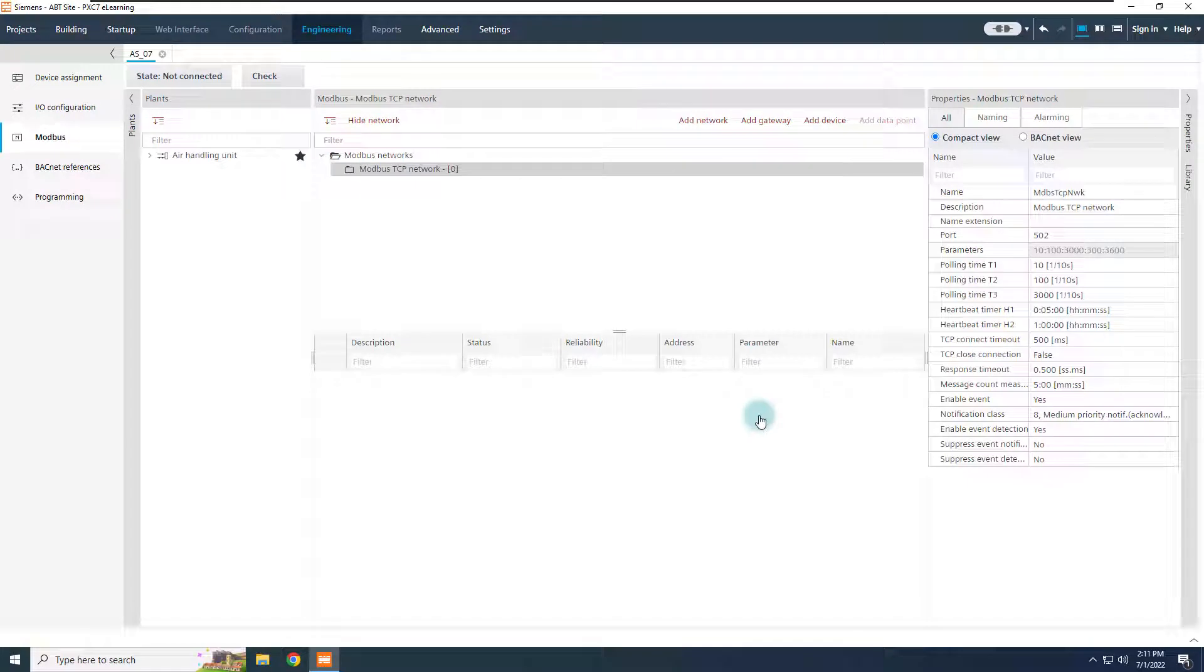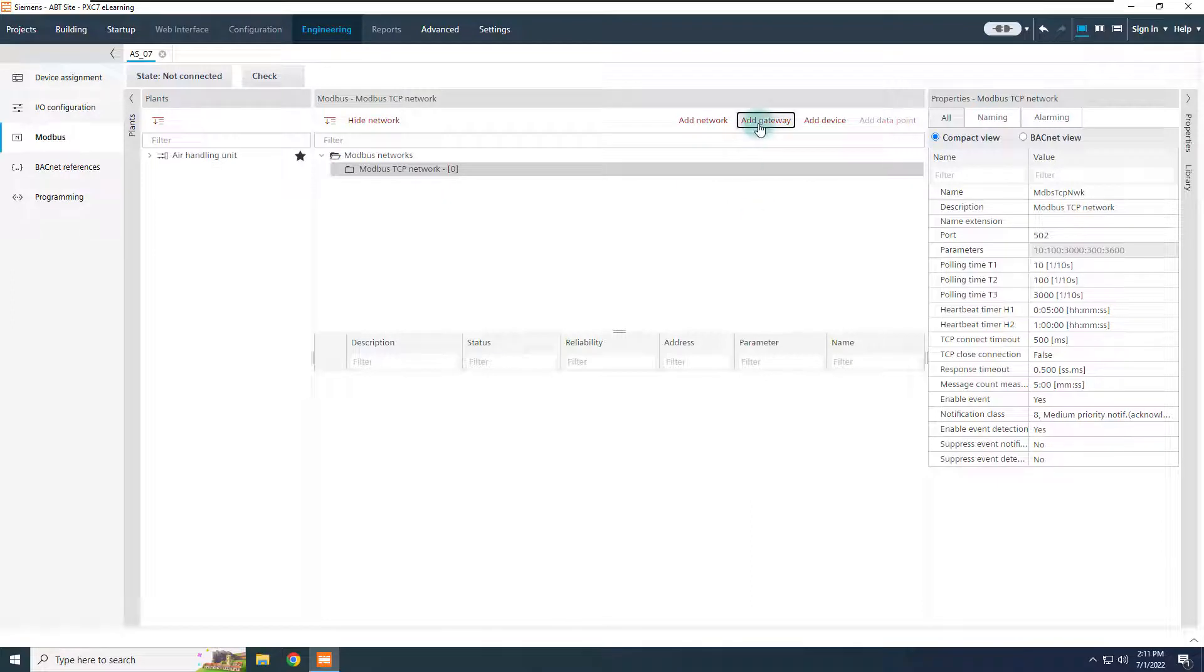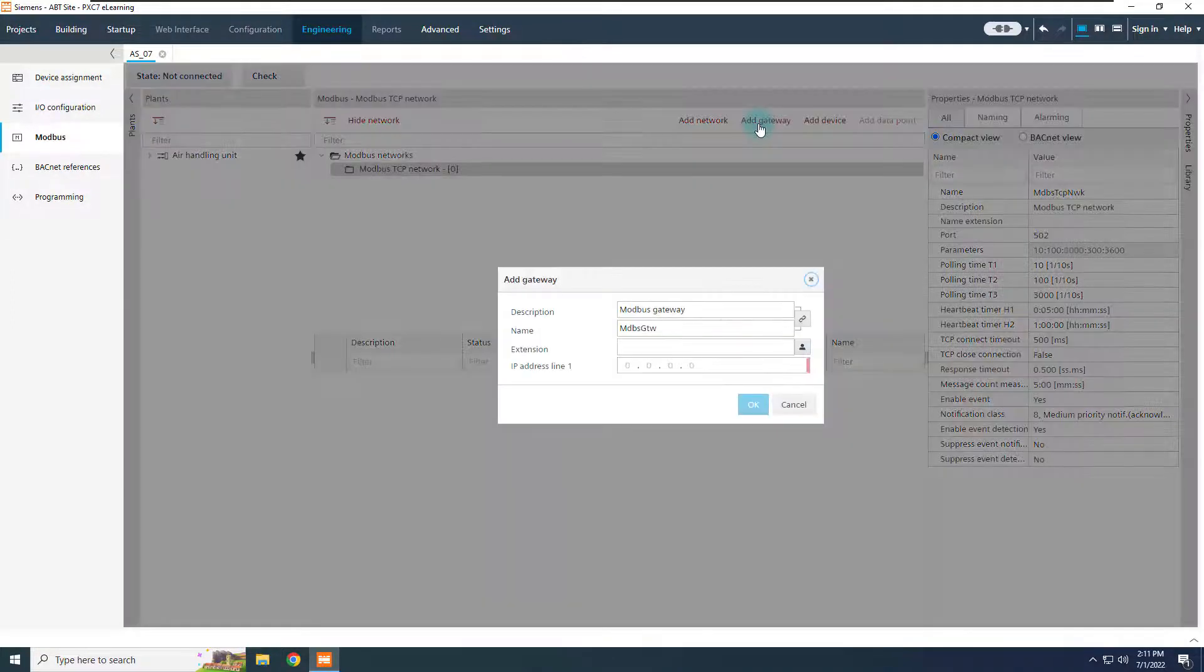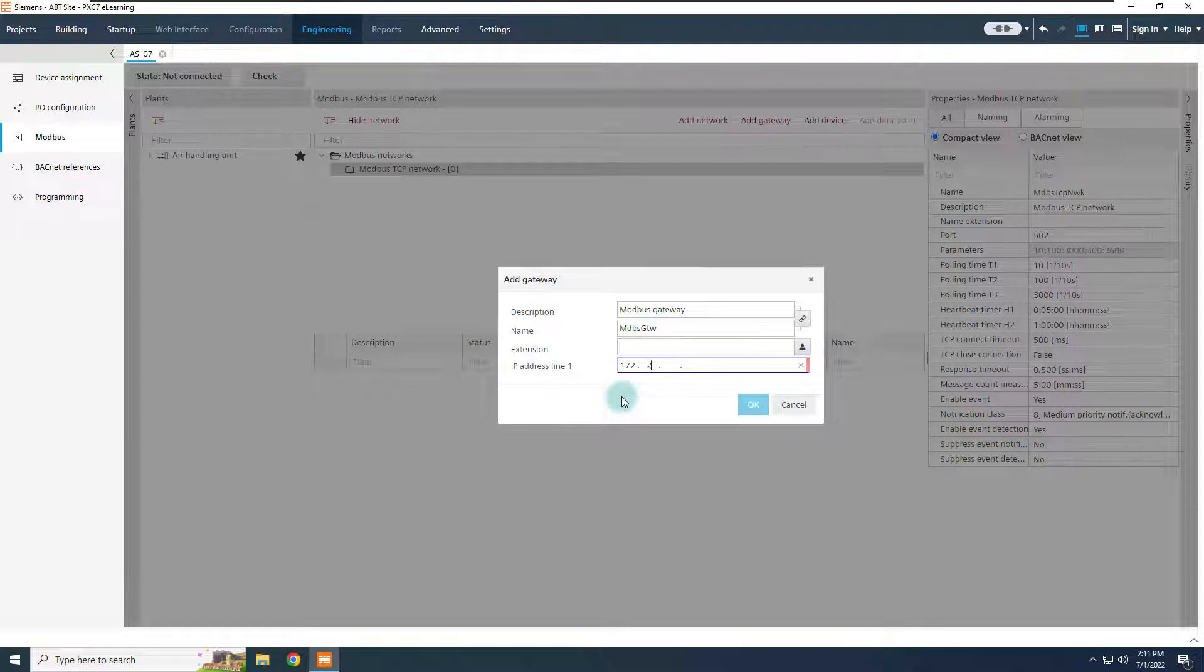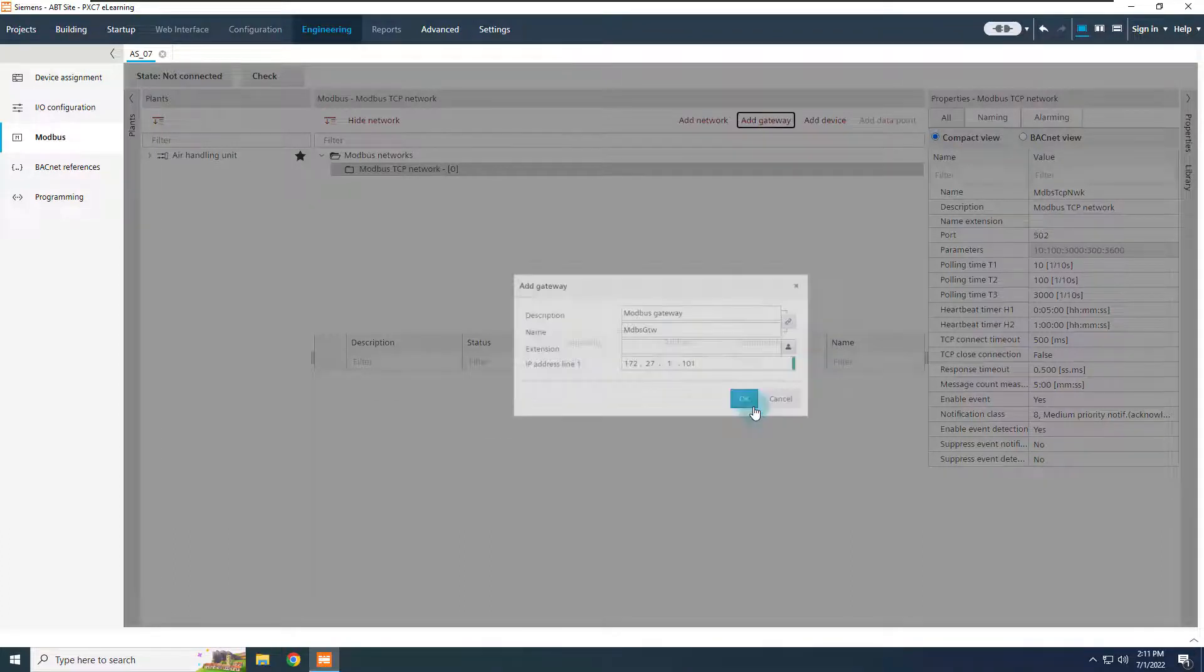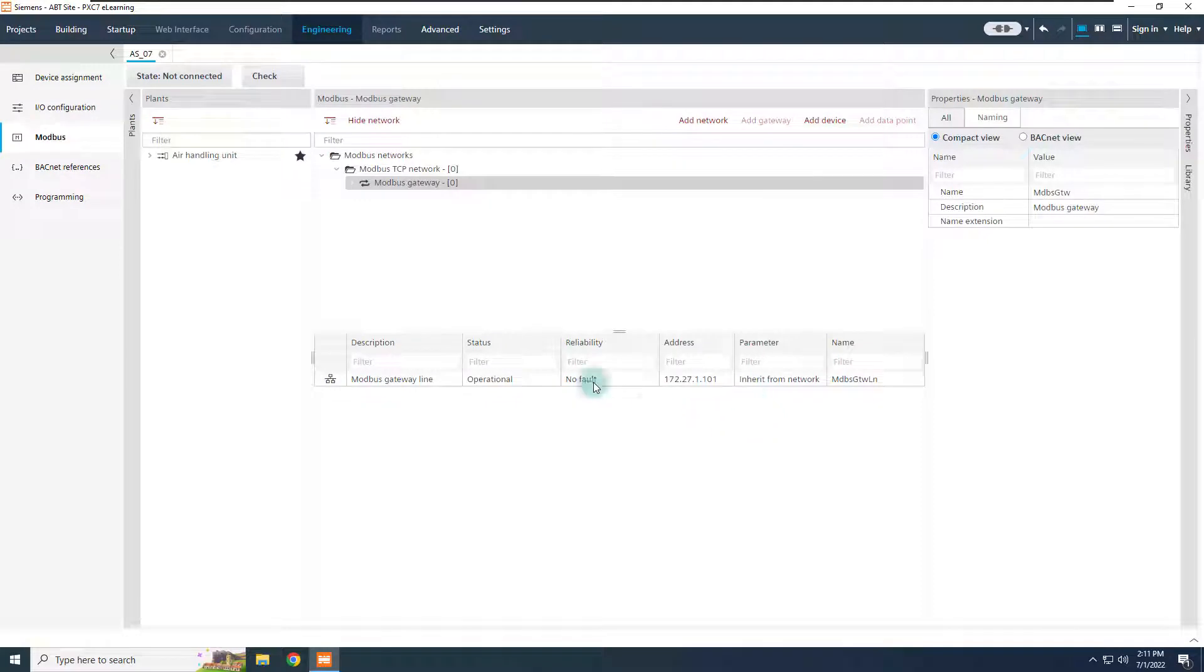From the new Modbus TCP network node, add now a gateway, and define the IP address of the first line, which is, in our example, 172.27.1.101. Once confirmed, the gateway node is created, together with the first line.